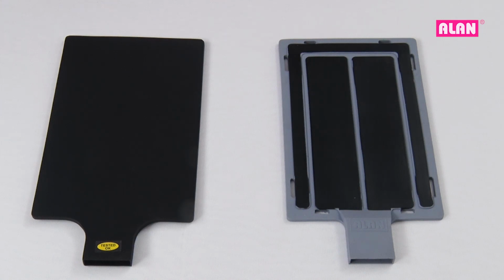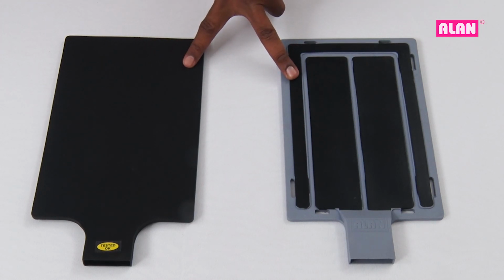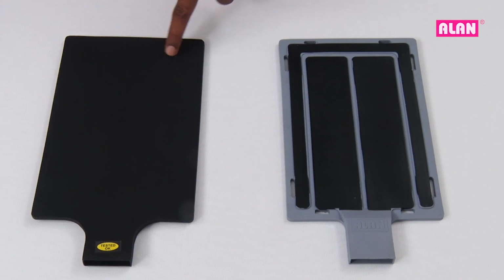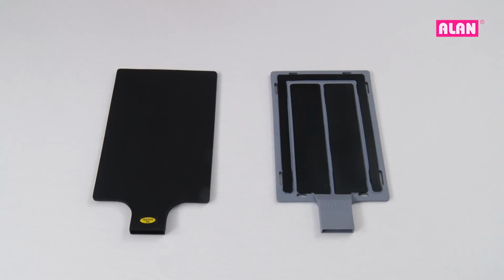Since we already saw the disposable patient plate in previous examples, we will look into these reusable patient plates. These are made of silicone, and in some cases, single pad silicone patient plate also comes in steel. If you choose to use reusable patient plates, always apply conductive jelly to the conductive area of the patient plate. After every operative procedure, clean the patient plate properly to remove the jelly thoroughly. Dried jelly may act as a non-conductor, resulting in malfunction and leading to unintended burns. Note: ALAN strongly recommends use of split type disposable patient plate for maximum patient safety.